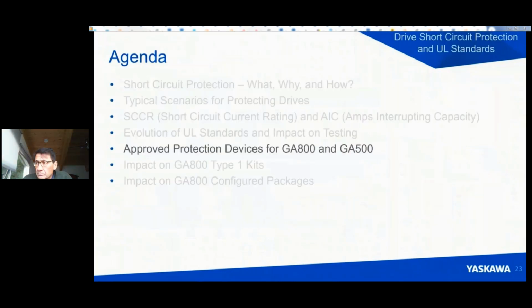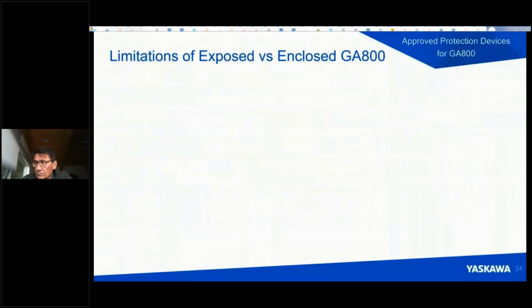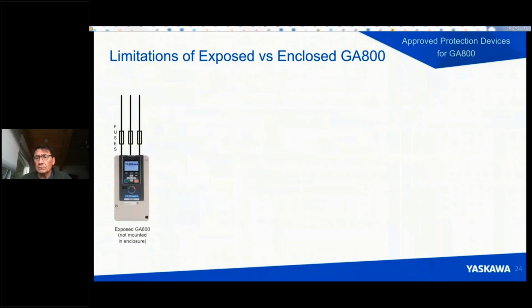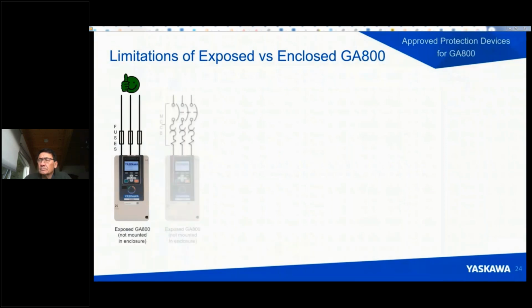Okay, next let's talk about approved protection devices for the GA800 and GA500, and what those limitations are. So first of all, let's take a look at a couple different scenarios of enclosed versus exposed. And this is a little bit of review, but it puts it in perspective pictorially. So when a drive is not mounted in another enclosure, I'm calling that exposed. We can protect it with fuses, and the fuses that need to be used are listed in our instructions. So this is a thumbs up. This is okay. This is good.